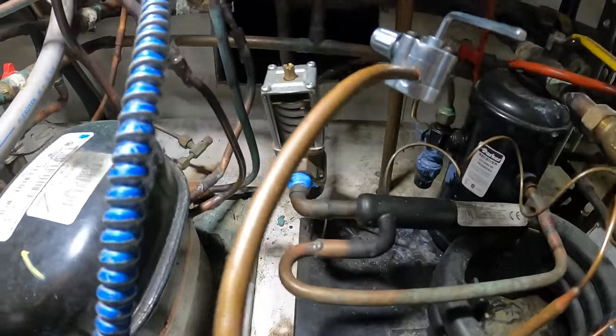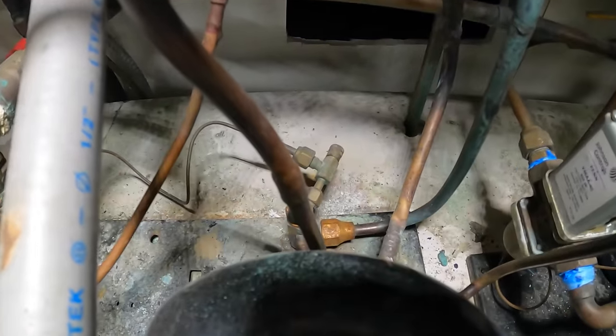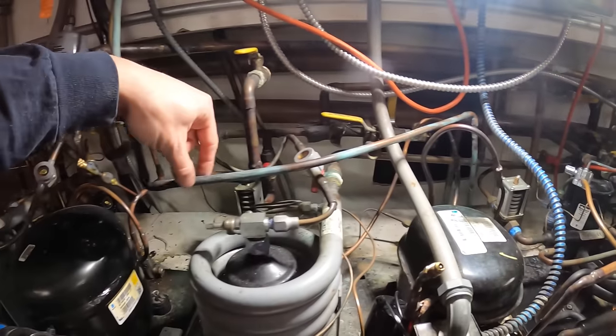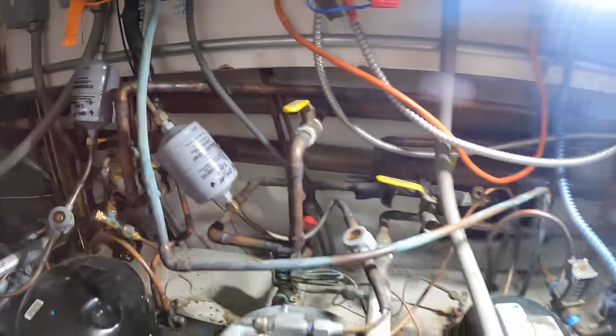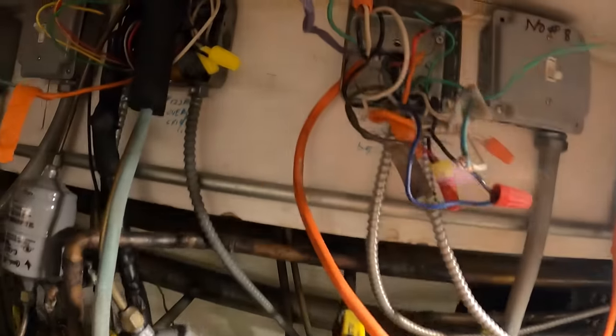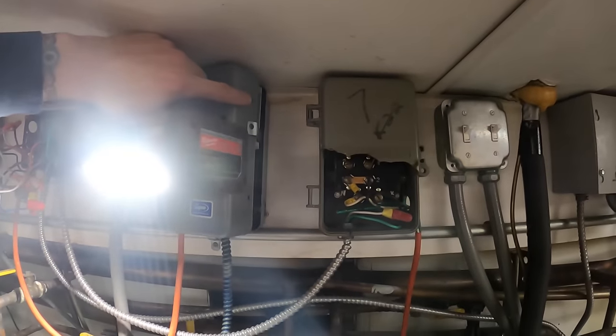There's also a kink in the pipe in the back. The suction line and liquid line both look terrible. The power coming from the thermostat — they're just cabled. Here's a defrost clock. It's seriously time for this thing to go.